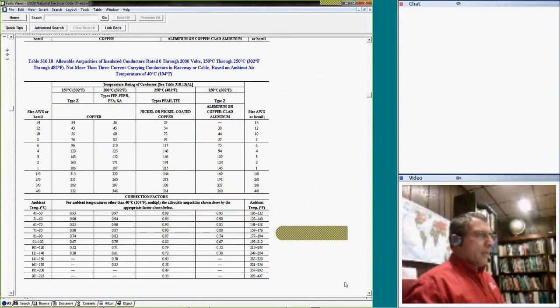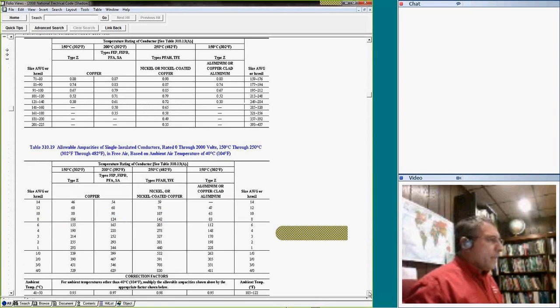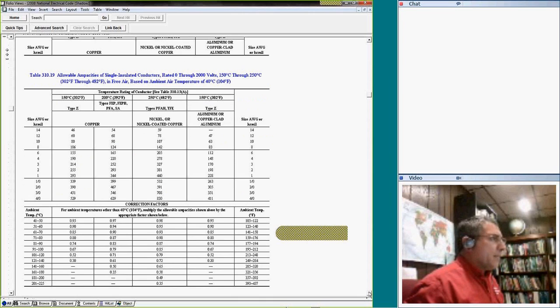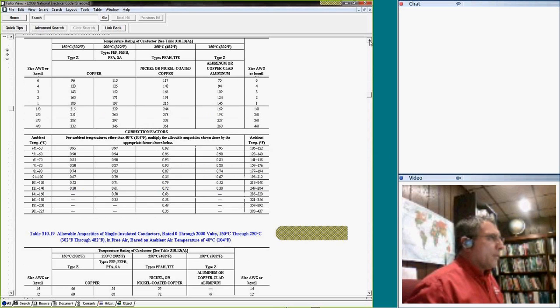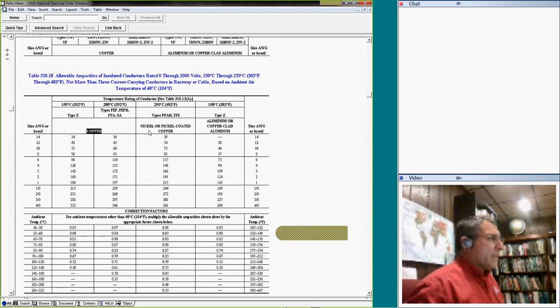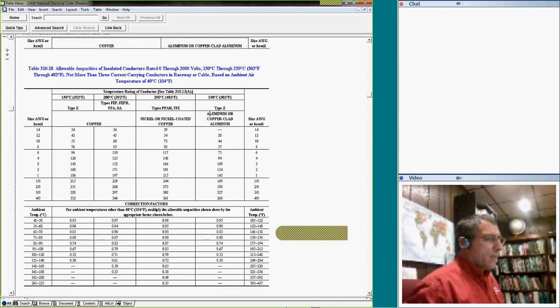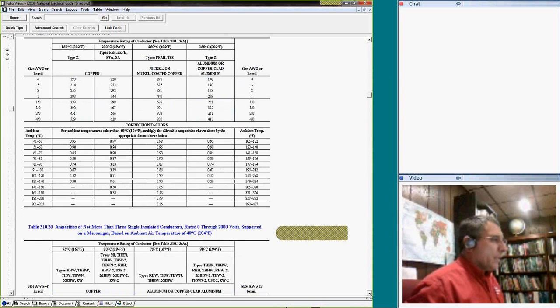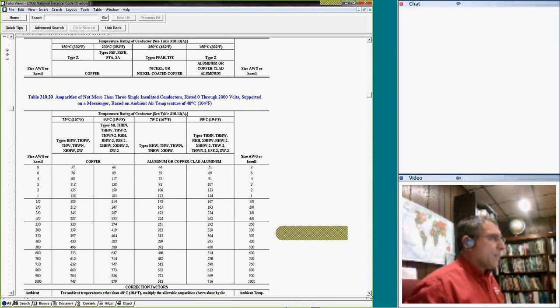Okay, let's close that one. And then you can see here there's also 250 Z. Some of them, look at the insulation type. There's copper, there's nickel, and nickel coated copper, and there's aluminum or copper clad aluminum. So these are the types of conductors. Nickel here too. I don't know if you've seen that, guys. Same thing, copper is nickel or nickel coated copper or aluminum. So there are two different types of conductors. So these are places to look at.